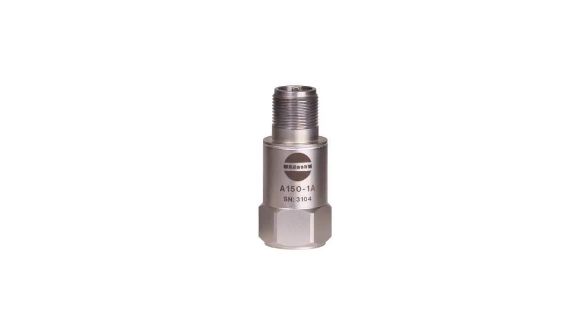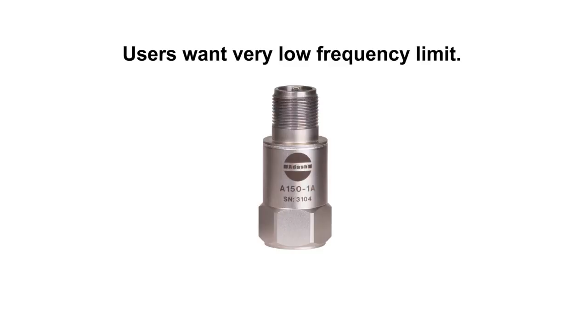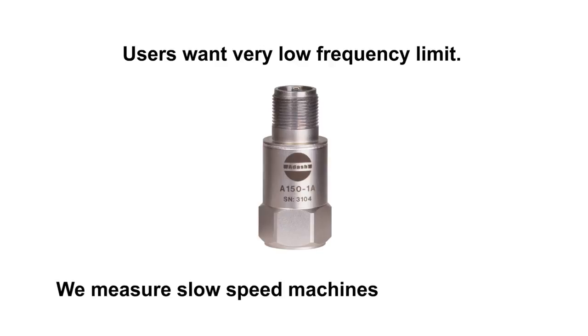Let's suppose the response function is flat. Most of the users want very low frequency limit. They say, I have to measure slow speed machine. They say, my machine speed is only 30 RPM. I need to measure on half Hz. If I ask them why, they do not answer. They do not understand this question.